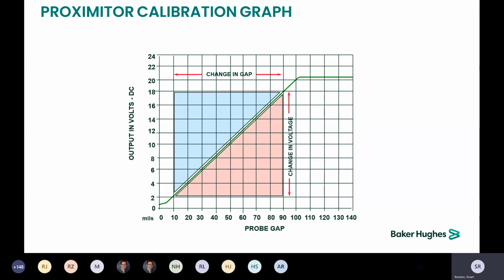system if everything is functioning as expected. And we also have it where it calculates the average scale factor for an 8mm probe. Should be in the 200 millivolt range per mil, but the specification allows for 188 millivolts per mil to 212 millivolts per mil. Most of the time I've seen them in the 195 to 205 range, which is within spec.